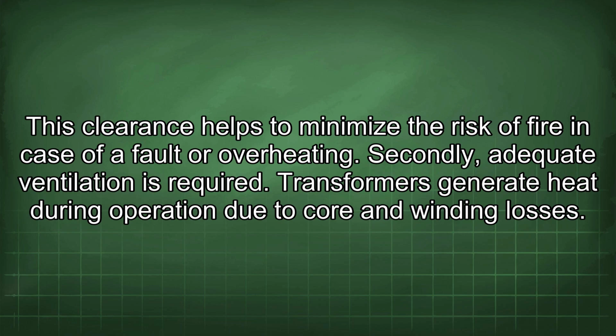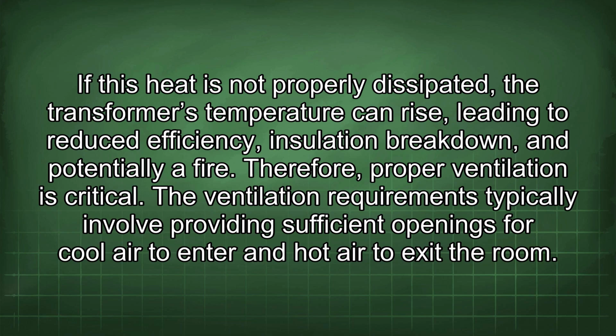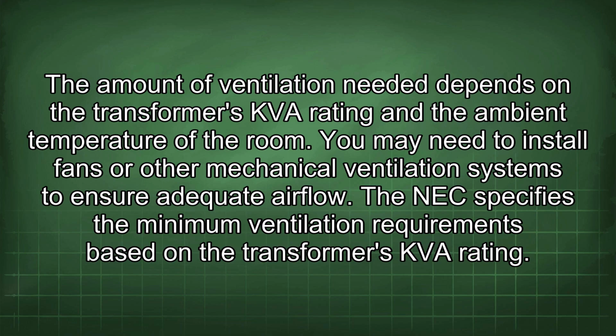Secondly, adequate ventilation is required. Transformers generate heat during operation due to core and winding losses. If this heat is not properly dissipated, the transformer's temperature can rise, leading to reduced efficiency, insulation breakdown, and potentially a fire. Therefore, proper ventilation is critical. The ventilation requirements typically involve providing sufficient openings for cool air to enter and hot air to exit the room. The amount of ventilation needed depends on the transformer's kVA rating and the ambient temperature of the room. You may need to install fans or other mechanical ventilation systems to ensure adequate airflow.